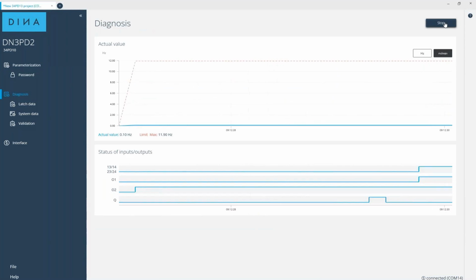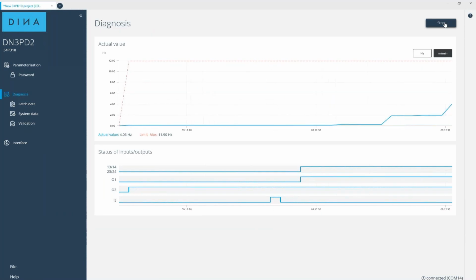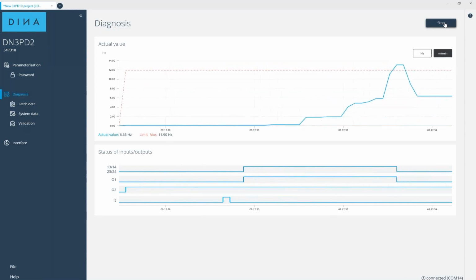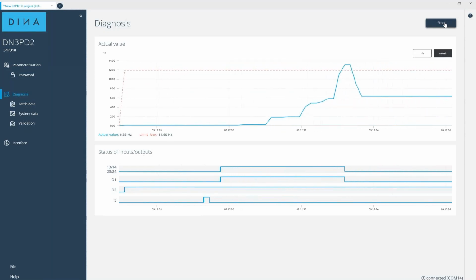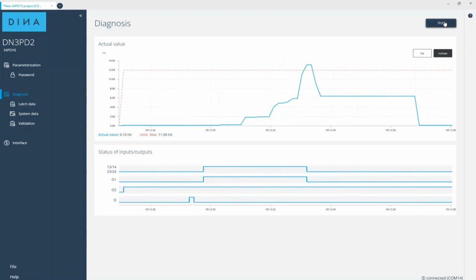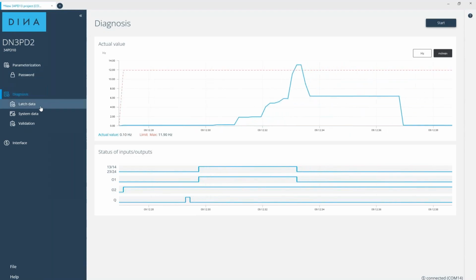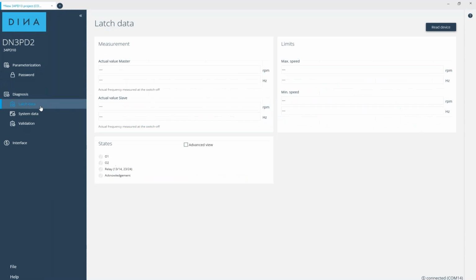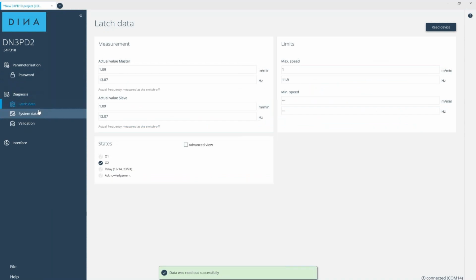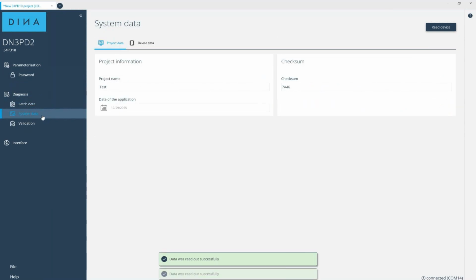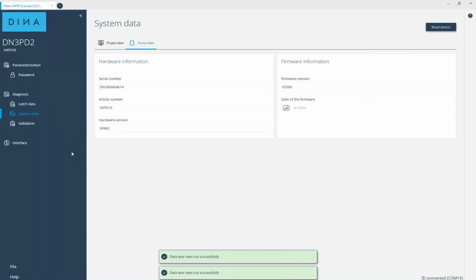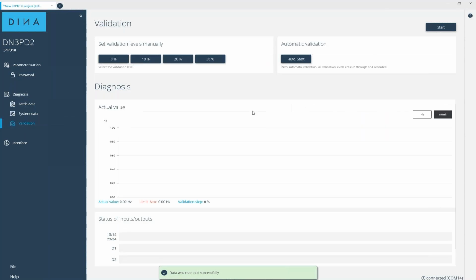In the diagnostic area, we had the option to see a live monitoring of the actual speed signal and the status of the safety outputs. This is crucial for immediately verifying that the device is operating correctly under different speed conditions. The view of latch data and system data provide necessary diagnostics information.